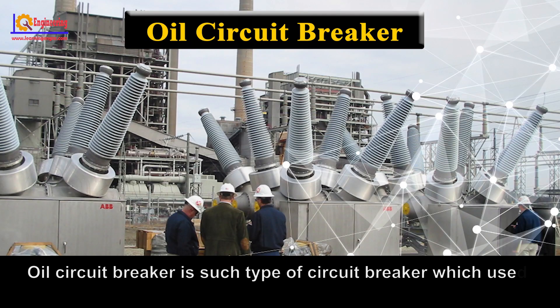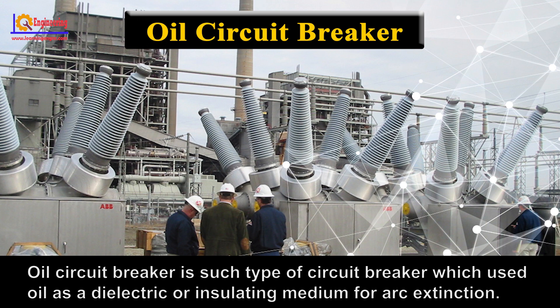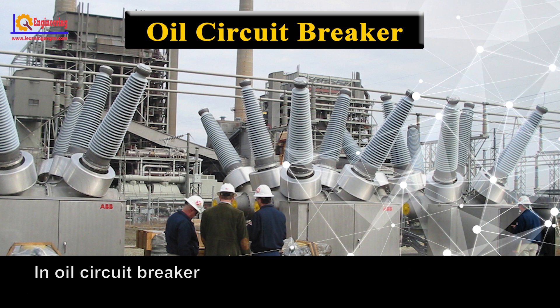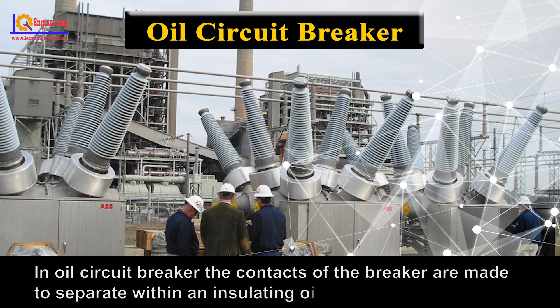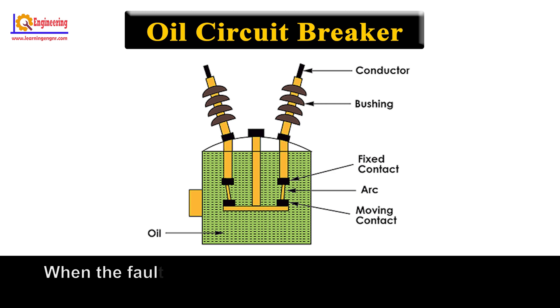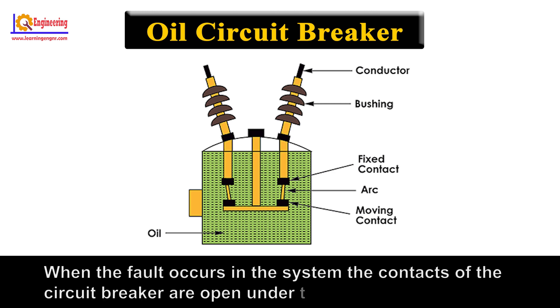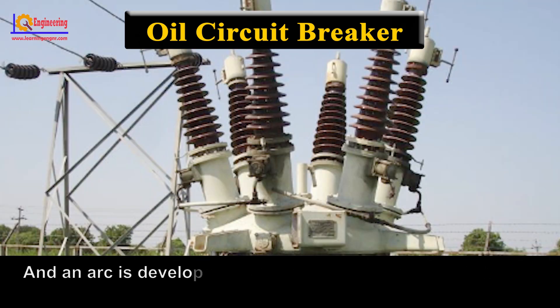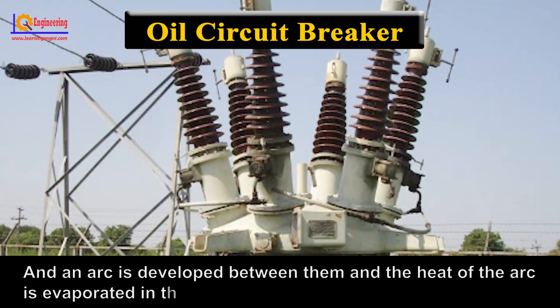An oil circuit breaker is a type of circuit breaker which uses oil as the dielectric insulating medium for arc extinction. In an oil circuit breaker, the contacts of the breaker are made to separate within an insulating oil. When a fault occurs in the system, the contacts open under the insulating oil, an arc is developed between them, and the heat of the arc is evaporated into the surrounding oil.